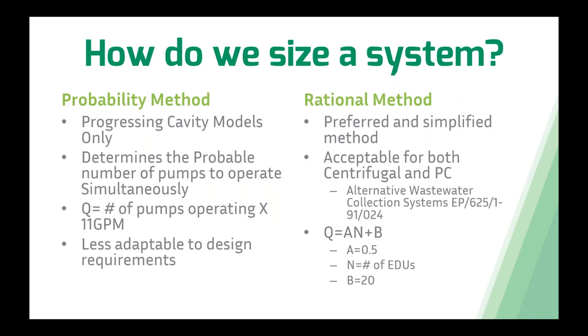The Rational Method is stated by the EPA as the preferred and simplified method for analyzing pressure sewer systems. It is acceptable for both centrifugal and progressing cavity systems and is adaptable to design requirements. The flow rate is determined by Q = aN + b, where a is typically 0.5, N is the number of EDUs (equivalent dwelling units), and b is 20. For 100 homes: Q = 0.5 × 100 + 20 = 70 gallons per minute. It is also more adaptable — commercial connections can be converted to EDUs based on daily flow rate, and the a or b values can be adjusted for all-commercial systems.